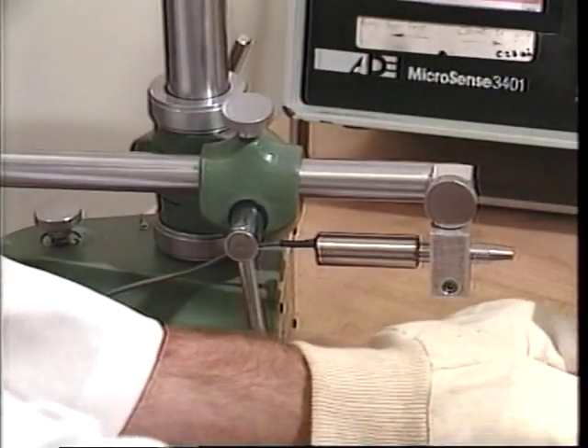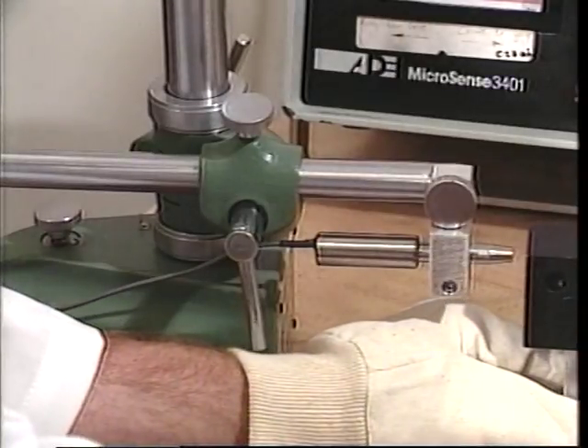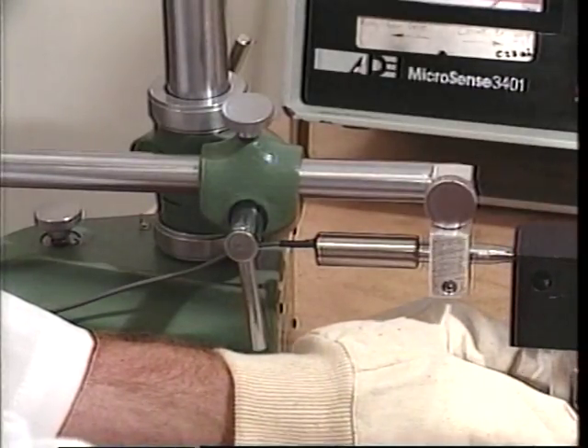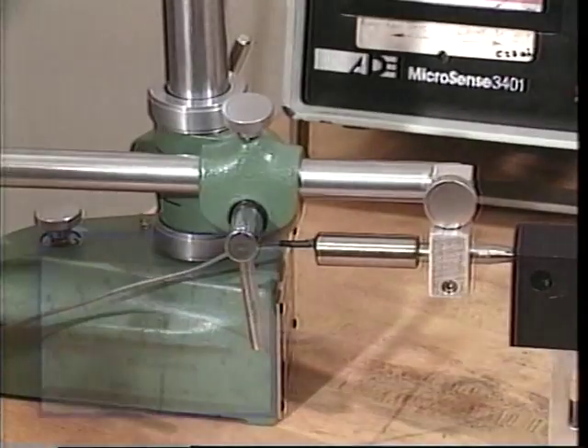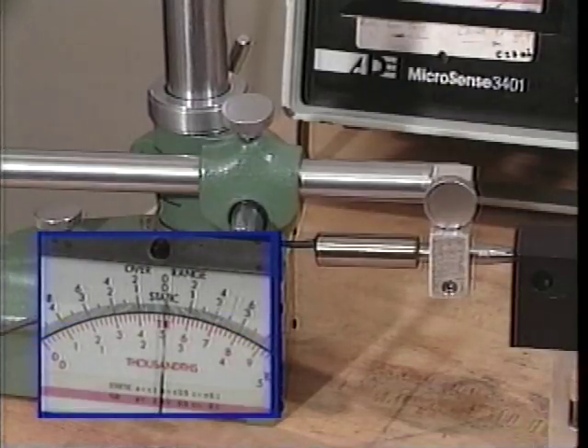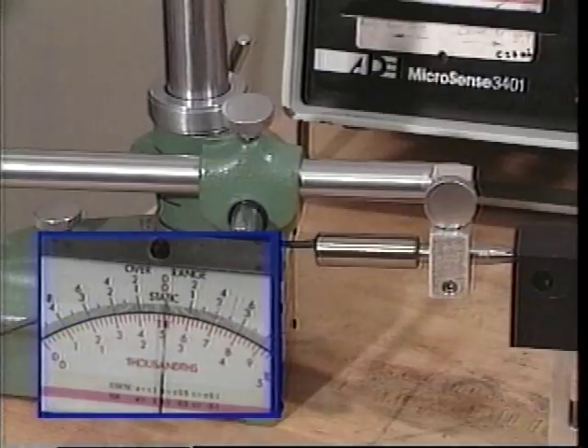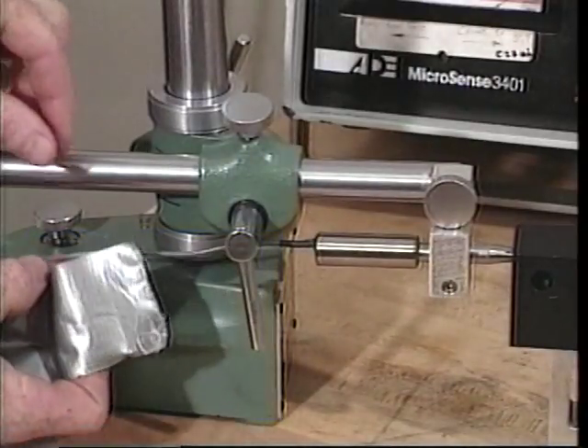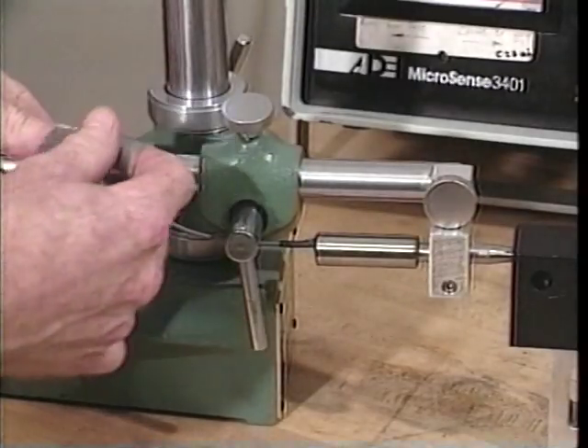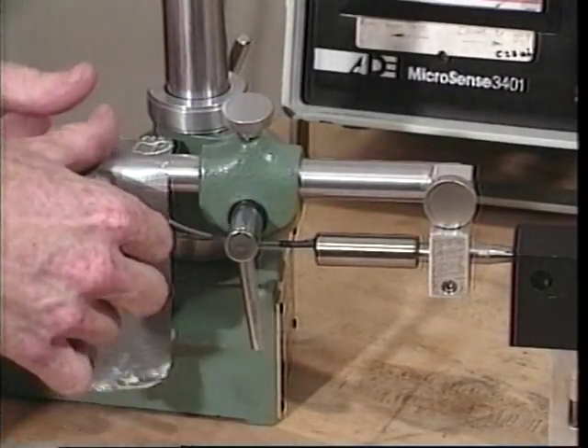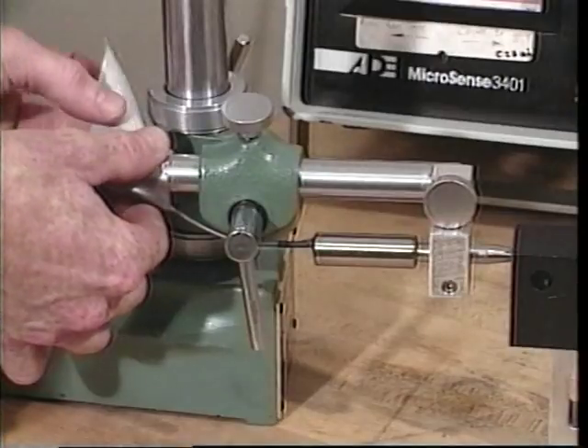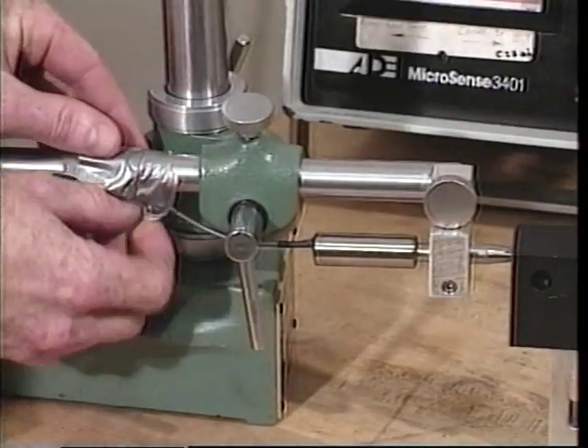Using a sturdy mounting fixture, carefully position the probe next to the target surface such that the display needle indicates 0. Remember, the target surface should be smooth and the target must be a conductor. If possible, wear gloves to minimize body heating of the equipment. Avoid contacting the delicate surface of the probe tip. Secure the probe cable, taking care to avoid placing it near sources of electrical noise. Allow time for thermal equilibration of the test equipment and the surrounding environment.